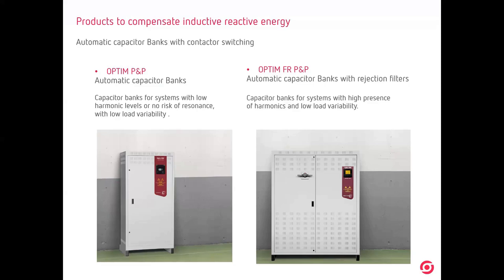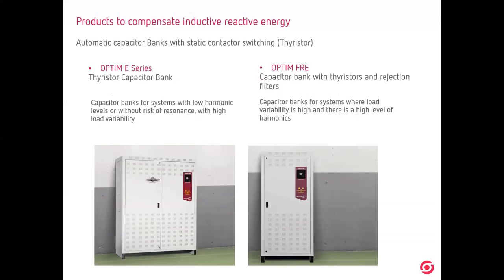But what happens if we are talking about an installation with fast, high load variability, like in automotive, for example, where we are using spot welding? Well, with a contactor, we will not manage to compensate the reactive energy because we are not fast enough, okay? We need a faster system. So those capacitor banks that you see, Optim E-series or Optim FRE, are capacitor banks working with thyristors. A thyristor is not mechanical, it's an electronic device. It's also better to use a thyristor because you don't have maintenance, because it's not mechanical. The contactor will die after some period of time because it's a mechanical thing. The thyristor, no, okay? You don't have to clean it like a contactor.